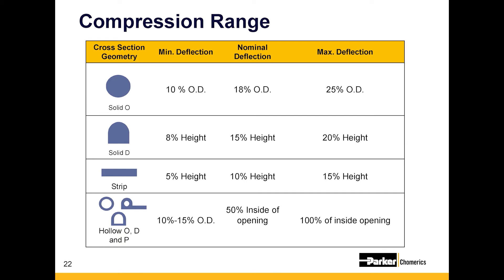It's really important to design your gasket to be properly compressed. These gaskets are filled with free-floating metal particles, so not having the minimum compression will prevent the particles from touching, and you won't get the shielding or grounding you're looking for. Conversely, exceeding the recommended compression value can crush the particles and reduce the gasket's ability to spring back after taking a compression set in heat or cold environments. Pay close attention to these compression forces.